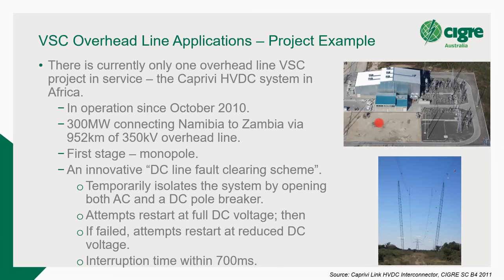But it has an innovative DC line fault clearing scheme where it temporarily isolates the system by opening both an AC breaker and a DC pole breaker, and then closes them back in. The issue here is it takes about 700 milliseconds, so it's pretty slow in comparison to, say, LCC restart capabilities. But this is likely a case where the system can handle the loss of this interconnector for that period of time.